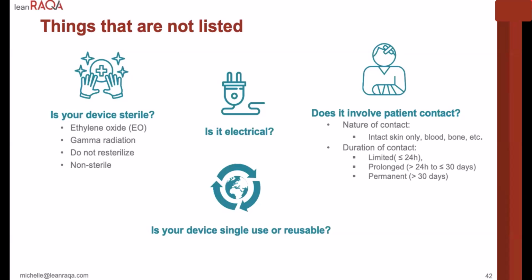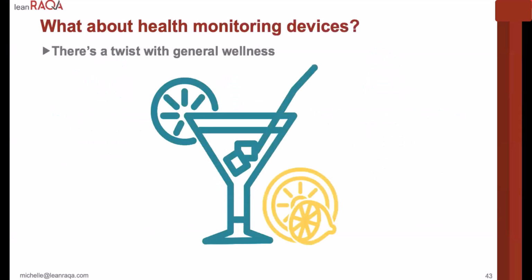These are all things like sterilization, electrical safety standards, biocompatibility standards based off of patient contact, reuse of devices. You have to look in a different database called the Recognized Consensus Standards to be able to find these more general and overreaching standards that will apply to your product.